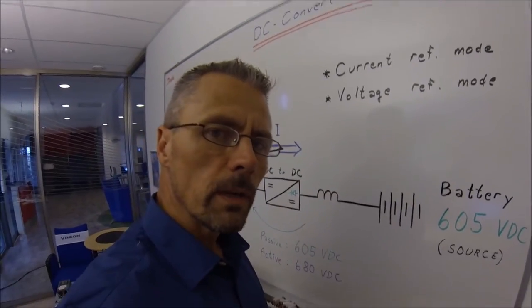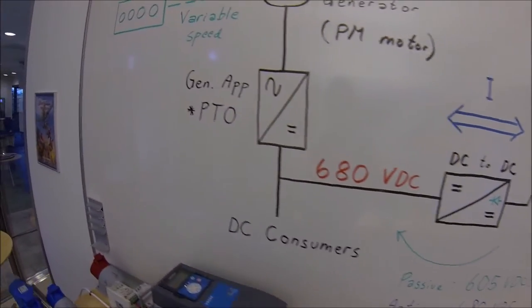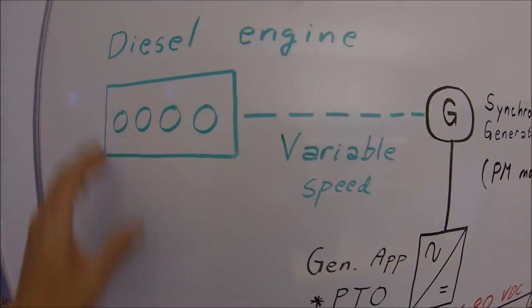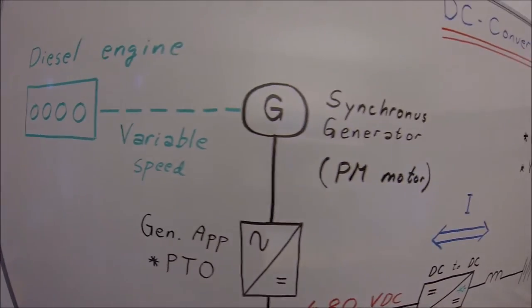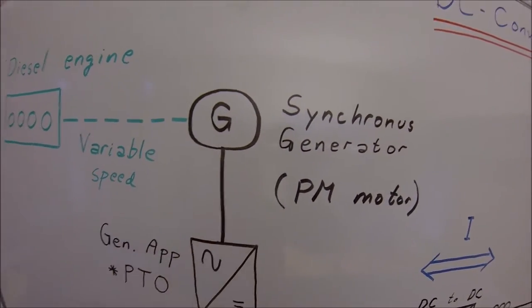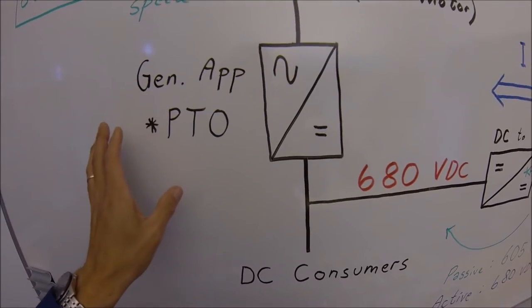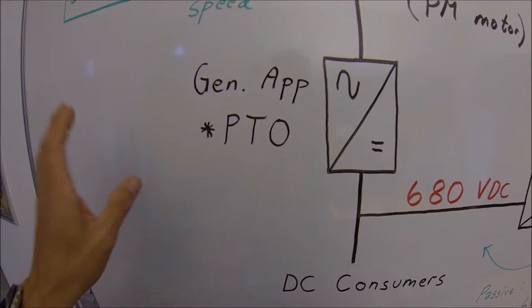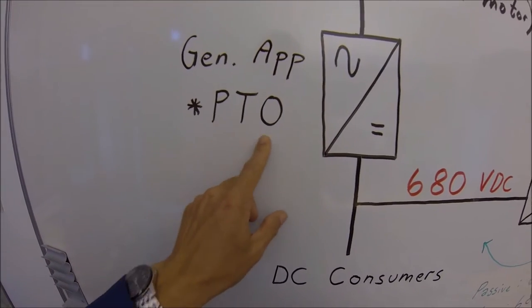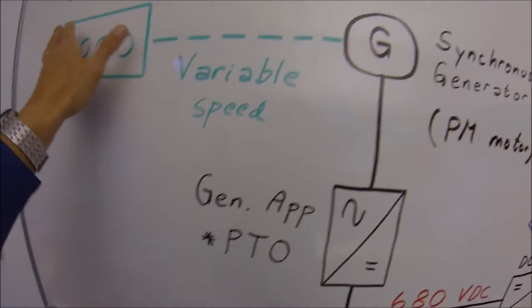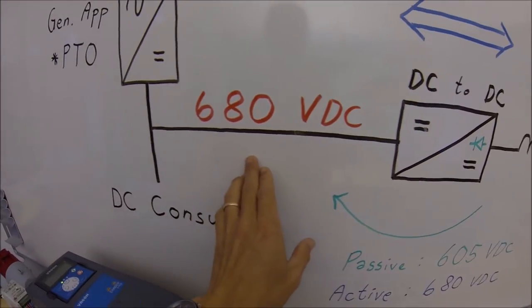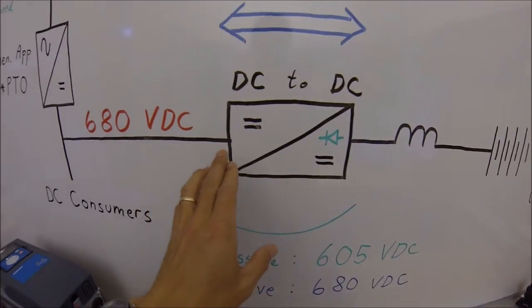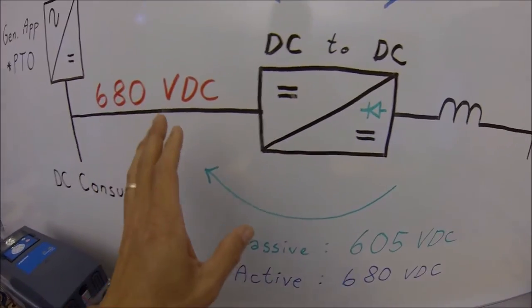One of the places where the DC converter comes in handy is when utilizing it on diesel generators. Diesel generators with variable speed, synchronous generator. In this case a permanent magnet motor. And now we have replaced the active front end with a generator application. Right now put into power take out mode. Now this generator application produces 680 volt DC. And we are going to utilize this voltage and energy source to charge the battery.